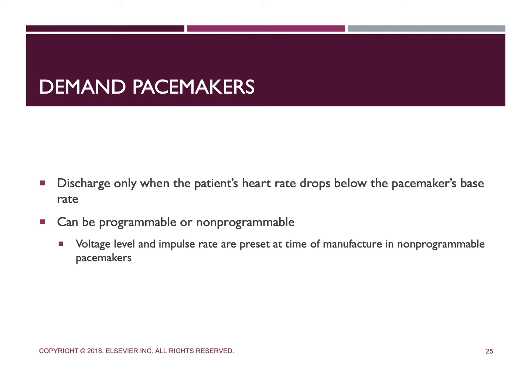A demand pacemaker, also known as a synchronized or non-competitive pacemaker, discharges only when the patient's heart rate drops below the pacemaker base rate. For example, if the demand pacemaker was preset at a base rate of 70 impulses per minute, it would sense the patient's heart rate and allow electrical impulses to flow from the pacemaker through the pacing leads to stimulate the heart only when the rate fell below 70 beats per minute. Demand pacemakers can be programmable or non-programmable. The voltage level and impulse rate are preset at the time of manufacture in non-programmable pacemakers.